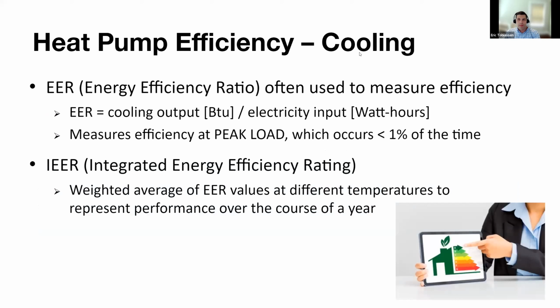Okay, so heat pump efficiency. This is going to be looking at the cooling side of your heat pump. So your EER, this is your energy efficiency ratio. This would be the same as what you'd see on a typical air conditioning unit at your house. So EER is just the cooling output divided by the electricity input. The big thing with EER is it measures efficiency at peak load. So this is your compressor, your system running as hard as it can. And this typically only occurs less than 1% of the time during cooling operation.